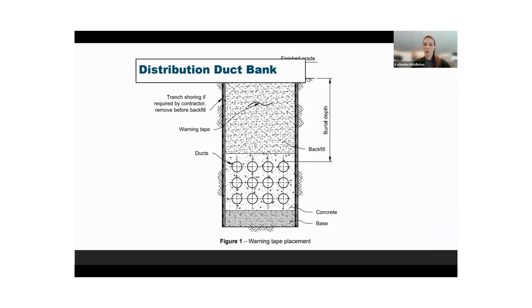For underground distribution lines, typically in more urban areas, we need to install duct banks for cables to move the electricity. This involves excavation, laying down the duct, and installing the cable in the duct. We usually like to pre-plan or install additional ducts for future development, if at all possible. Sometimes there'll be an existing duct bank in the area, but then we have some limitations if that duct bank is full or if we can pull additional cable or feeder through it.